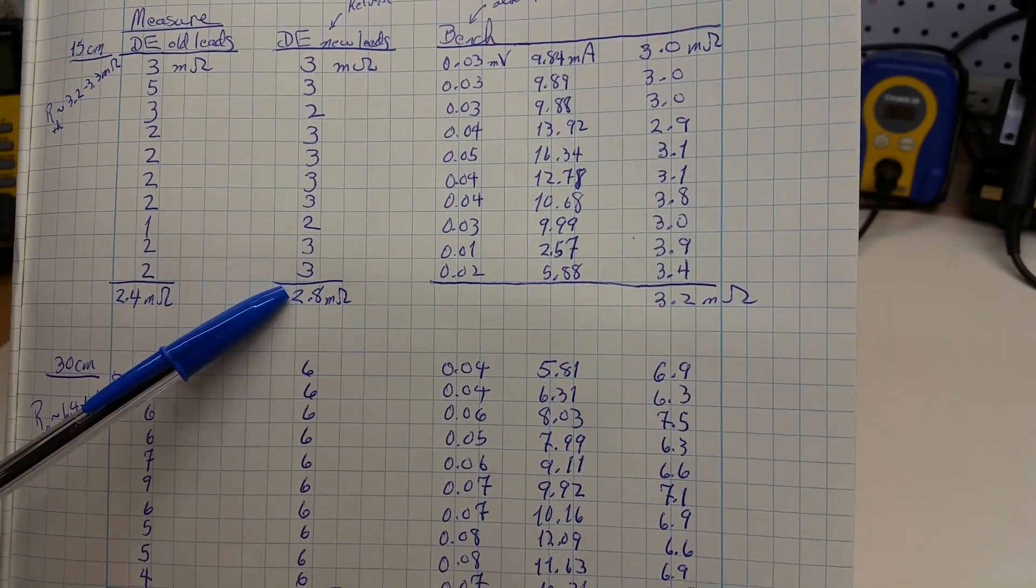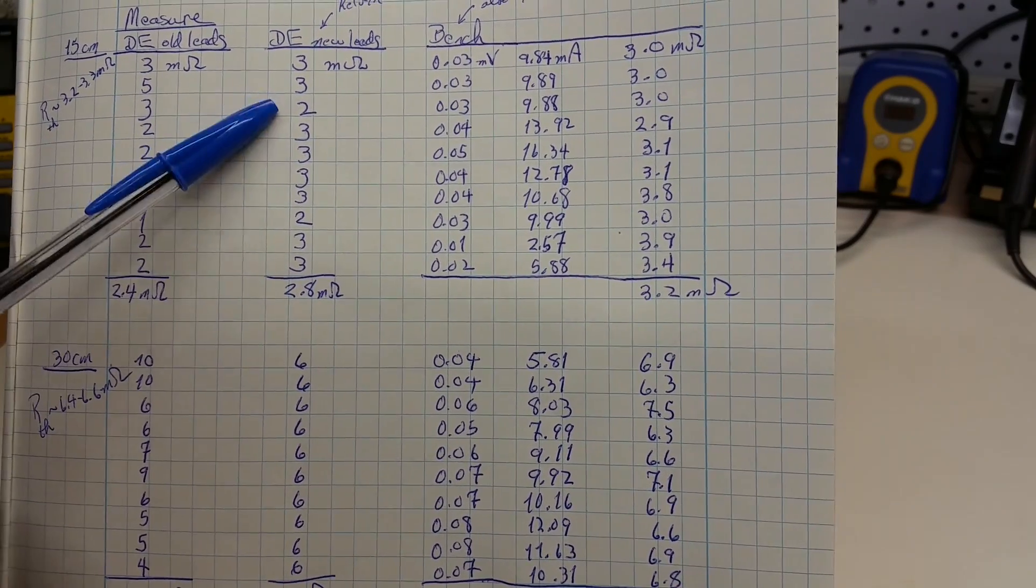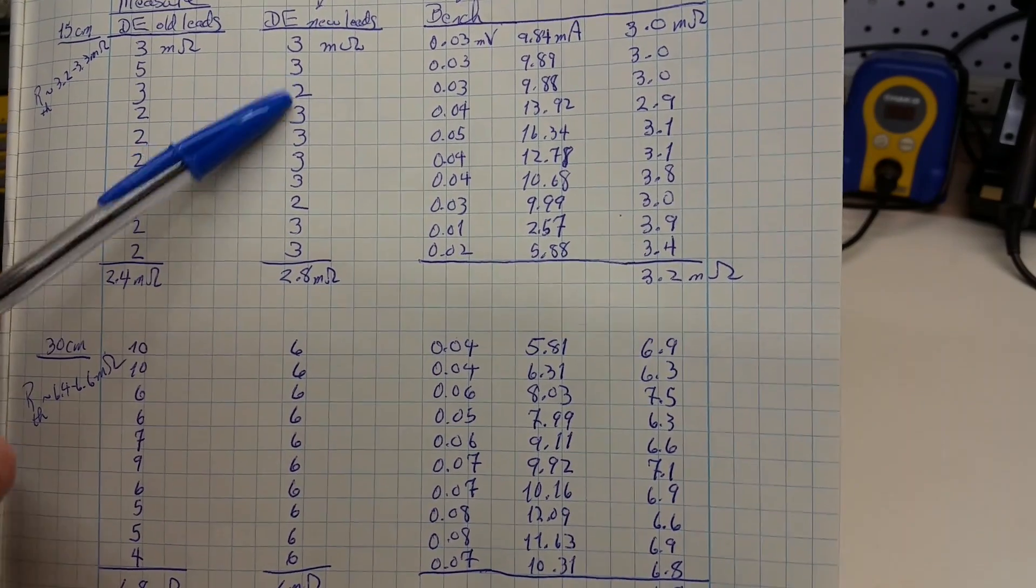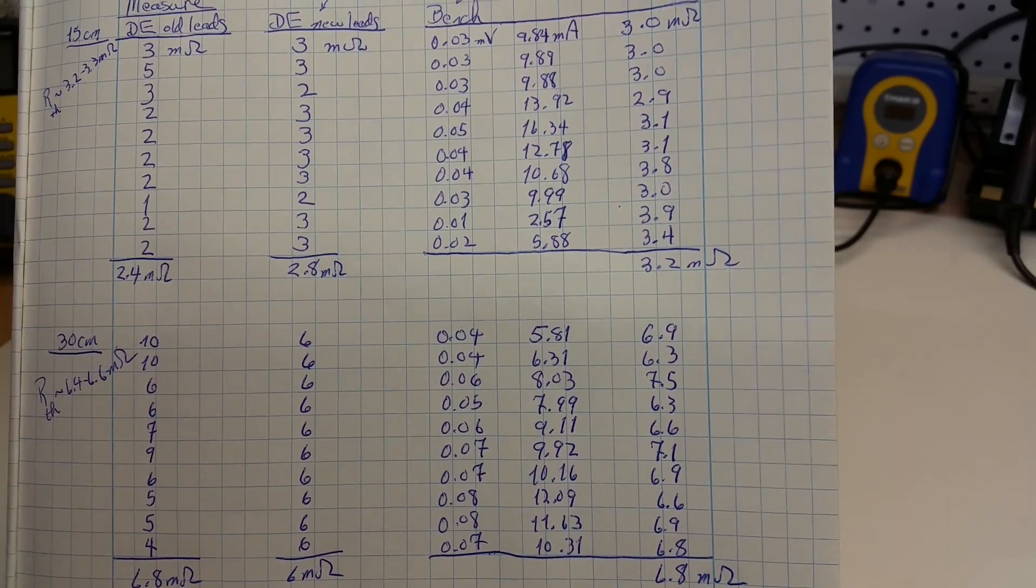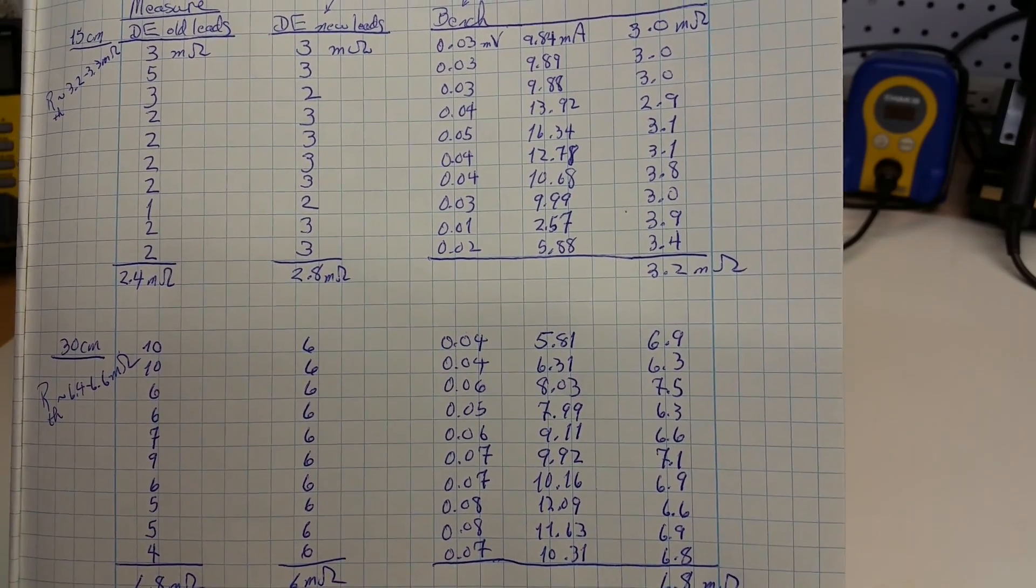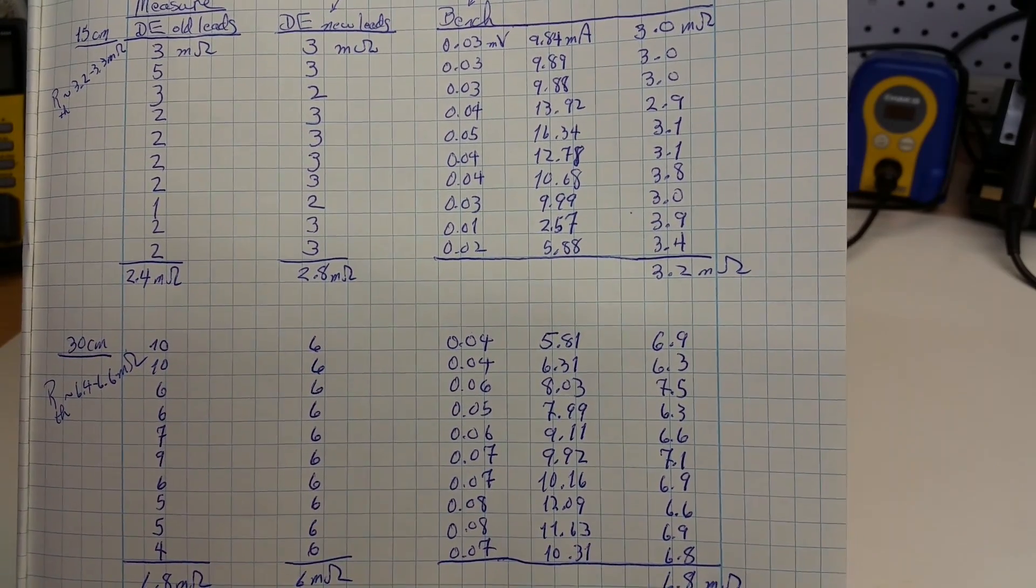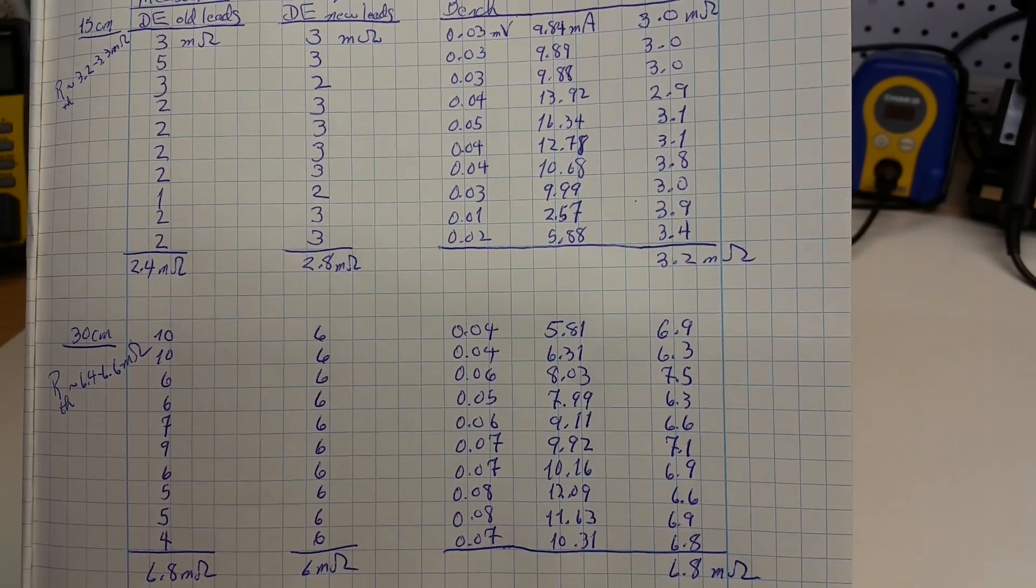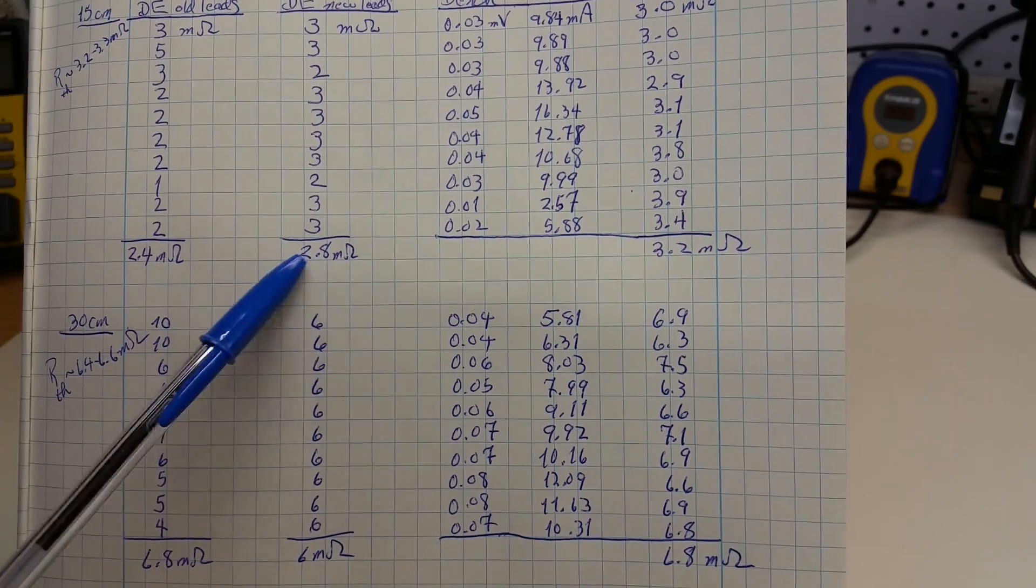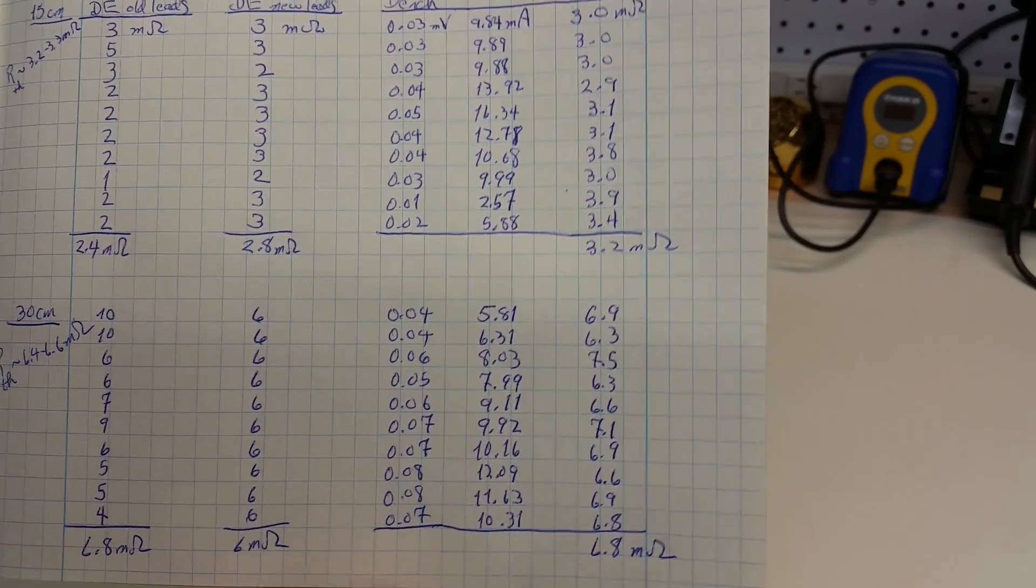In this range, there is some variability in the Kelvin clip-based measurement. There are almost all 3's, but there were two measurements where the meter measured 2 milliohms, giving an average of 2.8 milliohms.